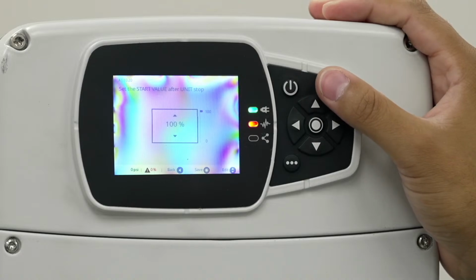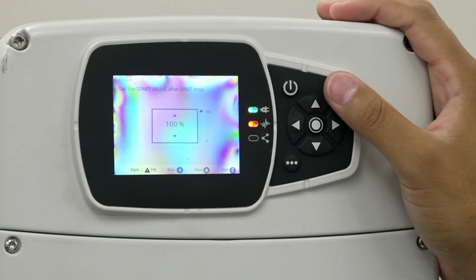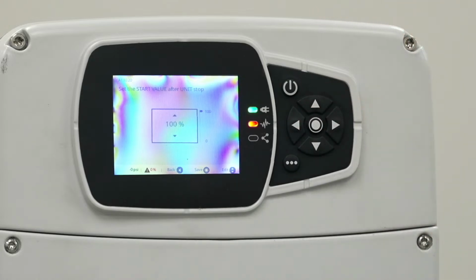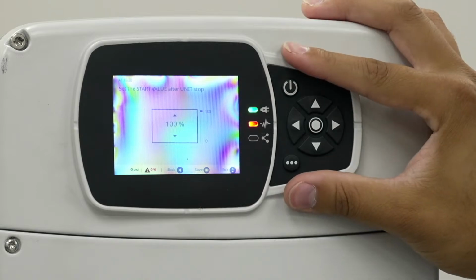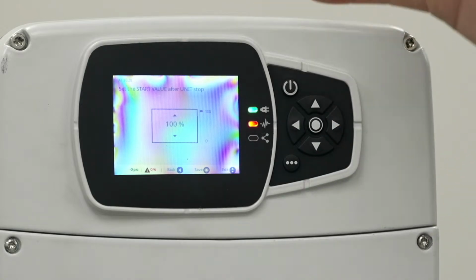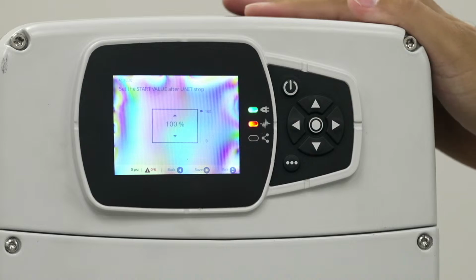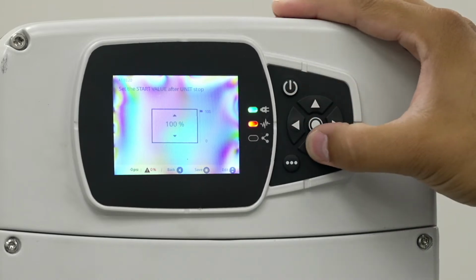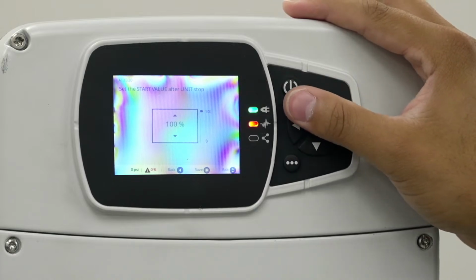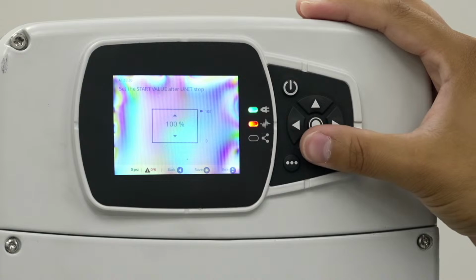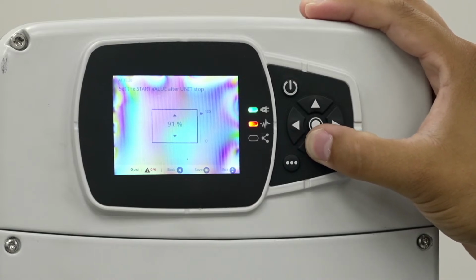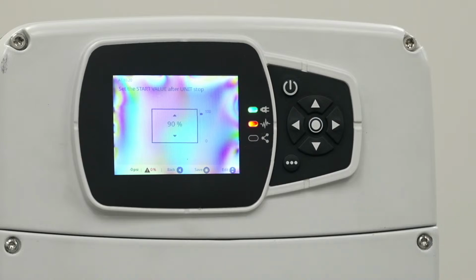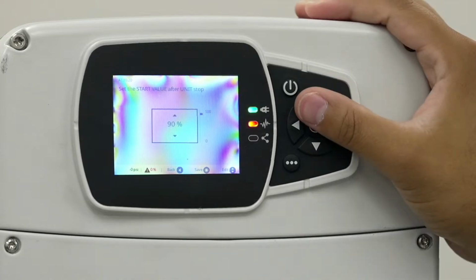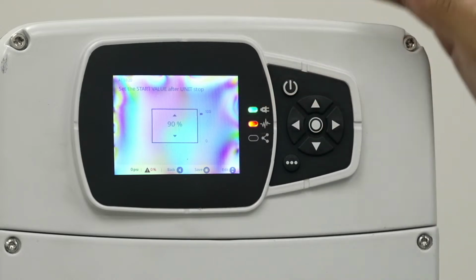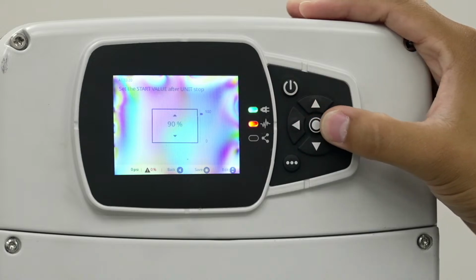And then the next question is the start value after the unit stops. So this is percentage based. Basically this is saying once this VFD has satisfied demand and it's turned off, right? It's slowed down, went to minimum speed. It's proved out that it's still meeting demand and there is no demand in the system. It's going to trigger the unit off. So now when is it going to wake back up? Here, 100% basically means as soon as it drops to 99%, it's going to kick back on. Obviously, we probably want some sort of buffer. So if I go to 90%, that's basically going to be a 10 PSI drop. Once the system demand kicks on, once that system pressure drops to 90 PSI, it is going to call this unit back on to maintain the 100 PSI set point we have.